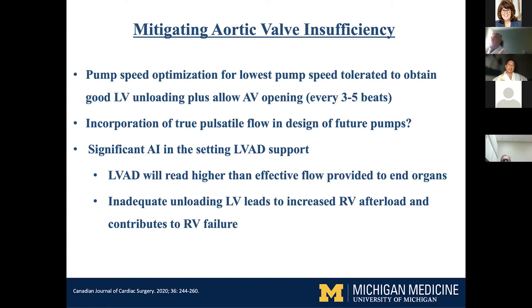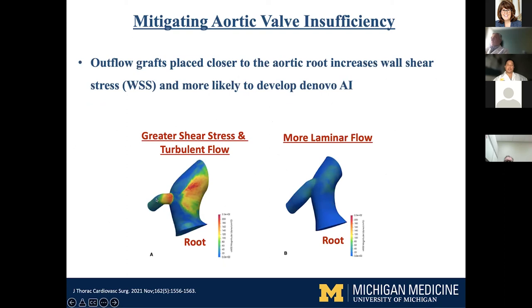What you see on the VAD when you have significant AI is that you'll read higher flows than the patient's clinical condition suggests — they're inadequately supported in terms of end-organ perfusion, but the LVAD is reading a good flow. The inability to offload the LV can lead to increased RV afterload and contribute to RV failure. Computer modeling also shows that if the outflow graft is aimed low, it shoots into the aortic wall causing turbulence at the root, which can promote AI development. Whereas pointing the LVAD a little higher, directing momentum toward the arch, produces more laminar flow and less turbulence at the root.